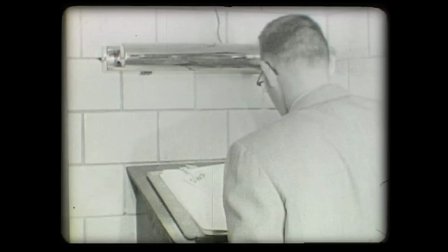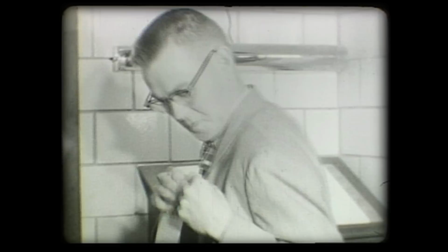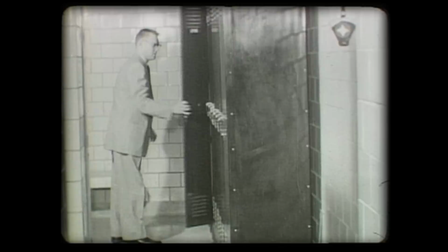We felt the control of unauthorized personnel in the Hot Canyon area could best be accomplished by using only one door and signing in and out. The laboratory provides special coveralls, shoes, and radiation instruments for all regular employees, with the locker rooms two floors above the canyon operations. The entire area is shielded by 2 feet of concrete. The safety of the worker was the primary concern in all of our planning. The wall around the stairway protects the worker from any stray radiation.